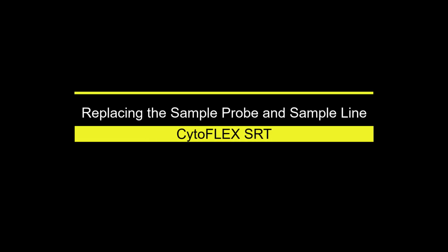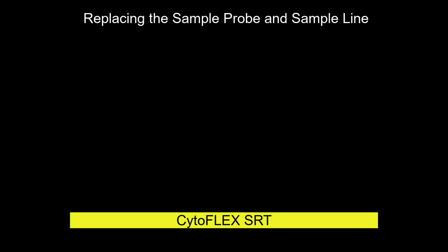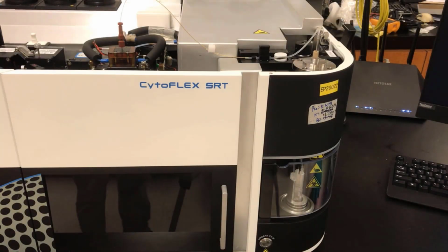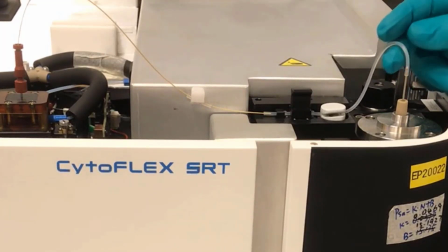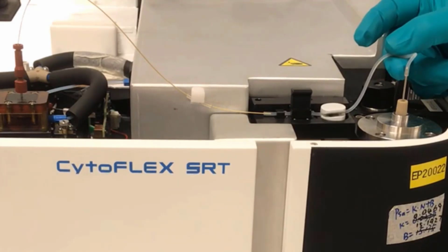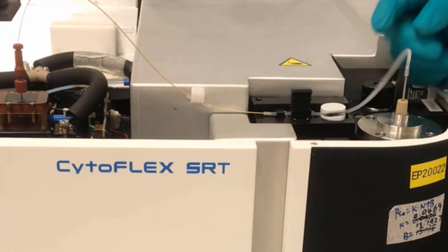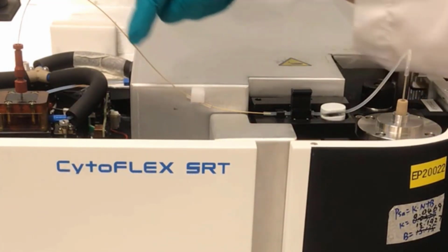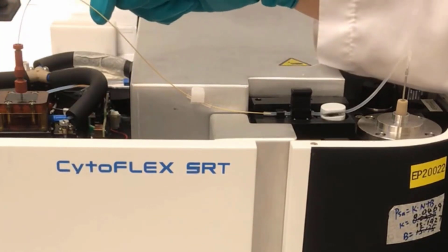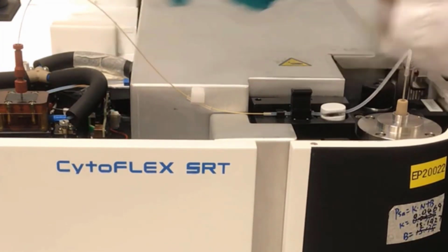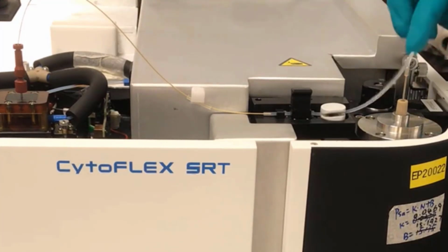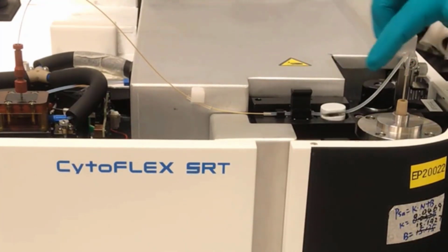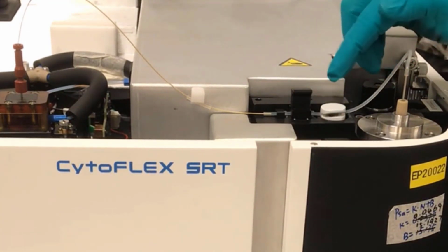This video will walk through replacing the sample probe and the sample line. The sample line has two sections. One section is silicone tubing. The other section is PEEK tubing, which is a hard tubing. The silicone tubing is soft. The soft tubing is used here because of the pinch valve that is used to open and close the sample flow to the flow cell.